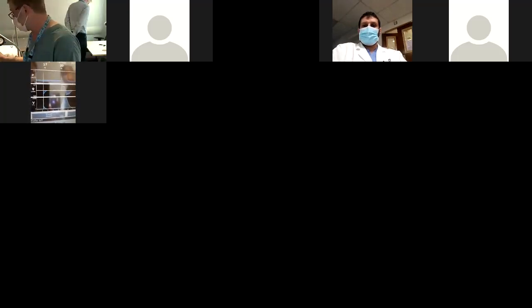Once again, same thing, color coded. Orange is inspiration, and blue is exhalation. And it's also over time. All three of these waveforms are over time. Anytime you're going to see a waveform, it's usually over time. So it's pressure over time, flow over time, and volume over time.